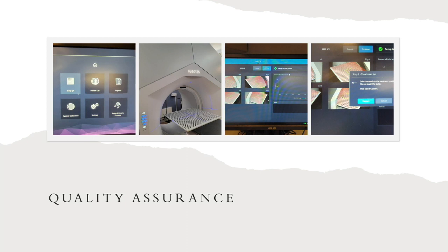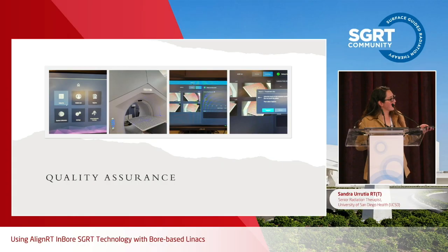So once we've selected the daily QA, we head over to the table and we put our polka dot board down and we set it up to setup ISO. Once we're at setup ISO, we capture the images using the external camera pods. We drive the couch into treatment ISO and take another set of images, and the system will check for the calibration of the two systems, so the camera pods and the inbore system, to verify that they are accurate.